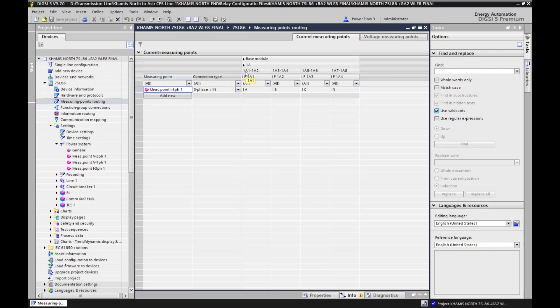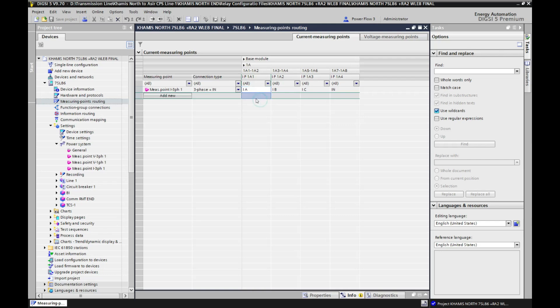Terminals 1A1 and 1A2 are available — for which phase do you have to assign here? If you click here, you can type. I put Ia. So what does this mean? Ia means red phase current. So our red phase current will pass through this. We have assigned that our red phase wire will connect to 1A1 and 1A2.